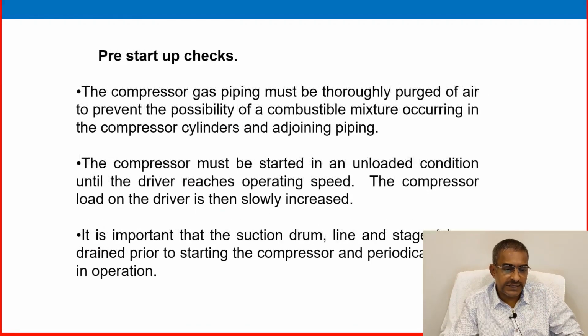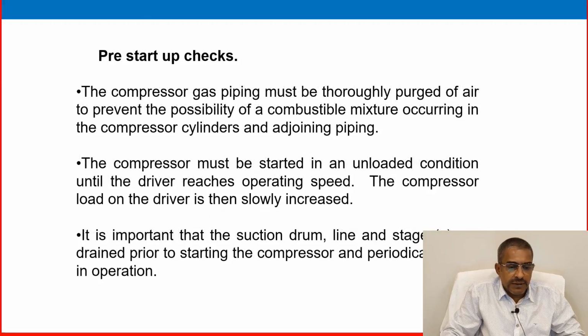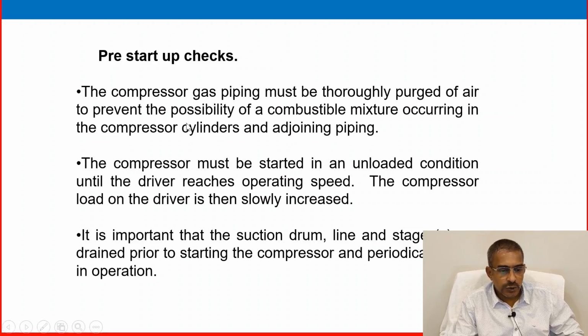So, pre-startup check. The compressor gas piping must be thoroughly purged of air to prevent the possibility of a combustible mixture occurring in the compressor cylinders and adjoining piping. The compressor must be started in an unloaded condition until the driver reaches operating speed. The compressor load on the driver is then slowly increased.